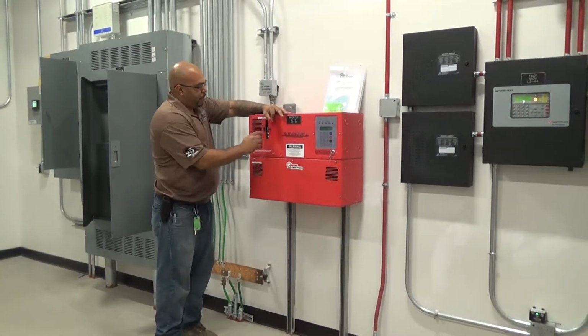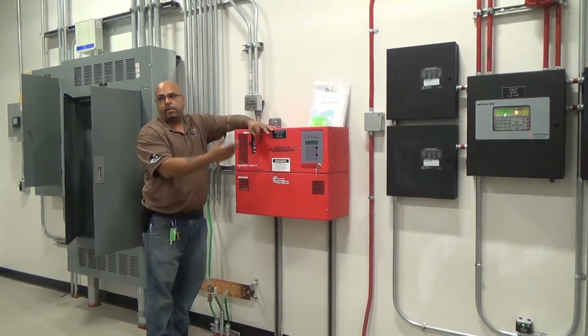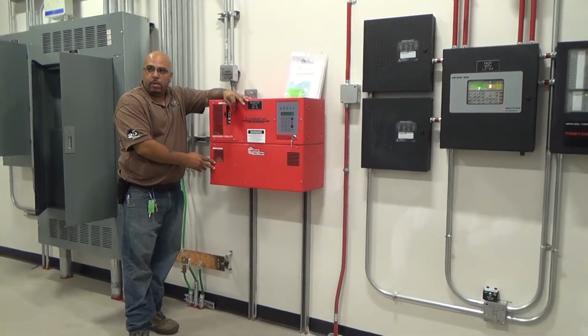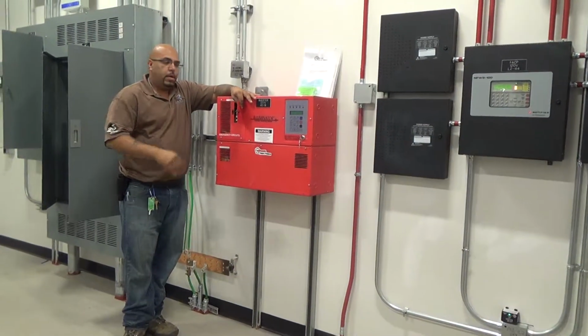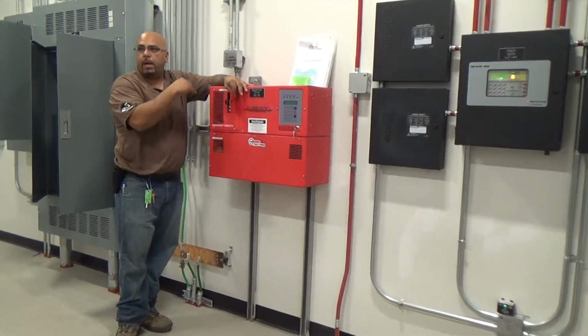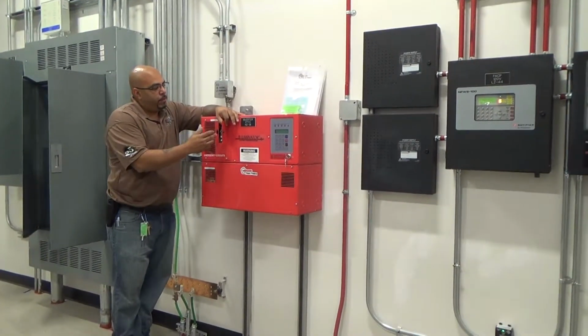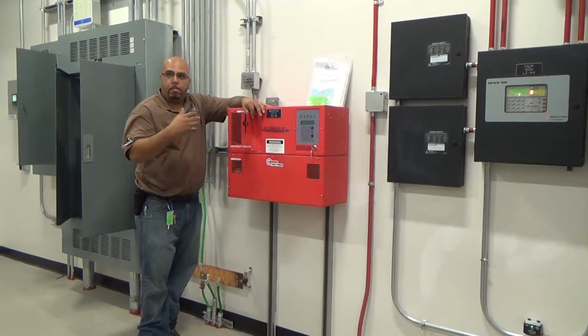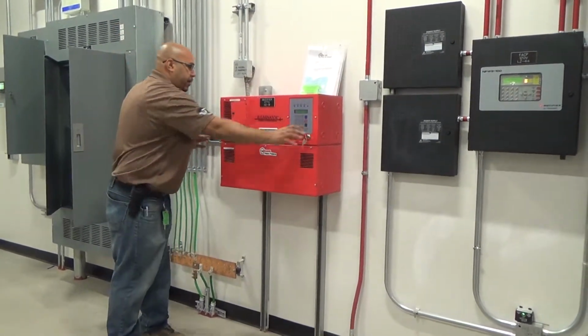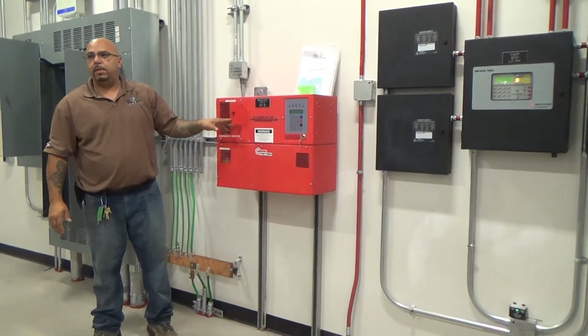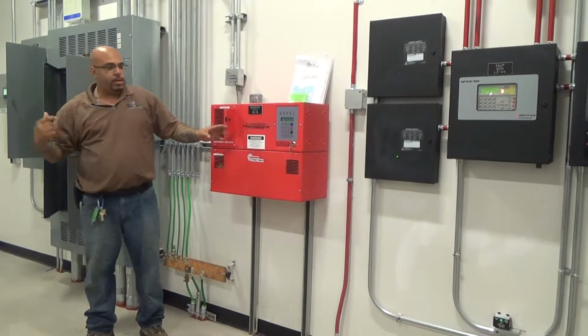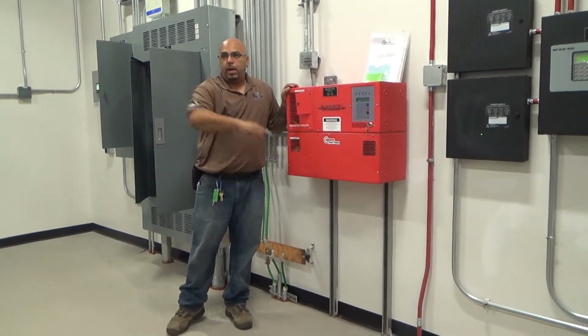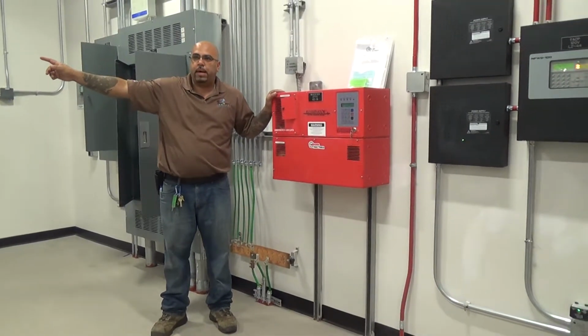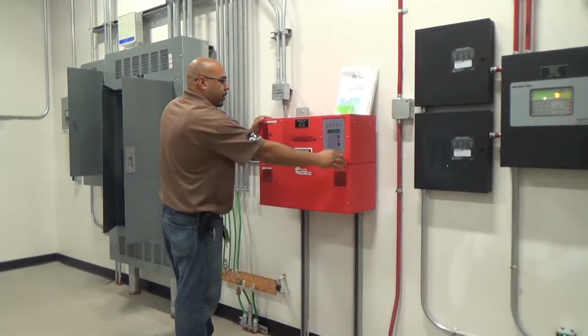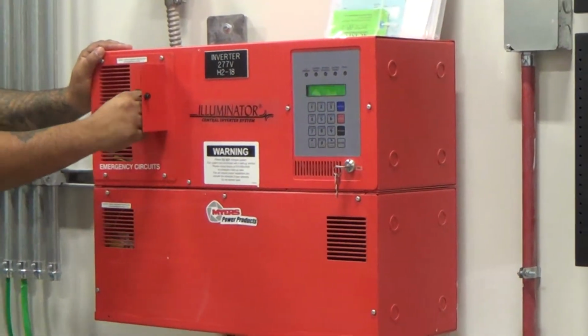If the building were to lose power, this inverter would automatically transfer over and go into battery backup. Okay? Once the building comes back up, the inverter will sense that the building has power and it will automatically transfer back over. But for precaution, if you have to work on it, the best procedure is to shut off the entire inverter with the input, output, and especially the battery. Because if you just shut off the breaker, it's going to read that the building lost power, and it's going to kick out 277 volts back to those fixtures through those batteries. Okay? And once you want to go back online, you just shut this all back on, and everything should come back on.